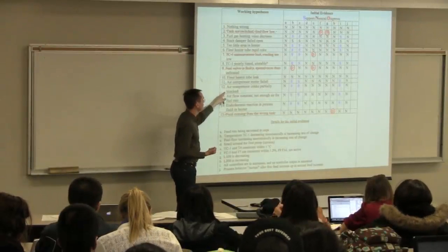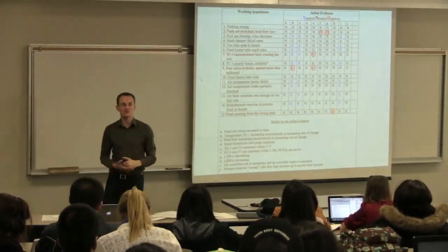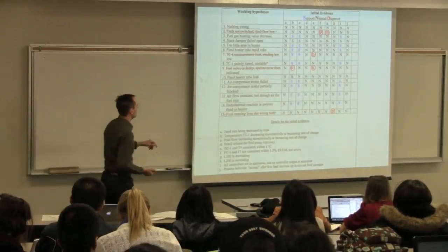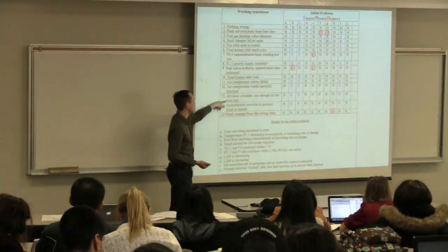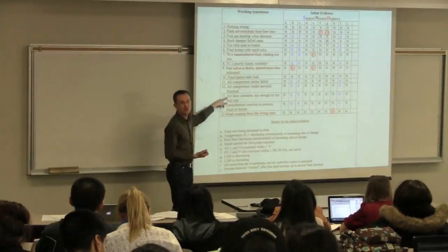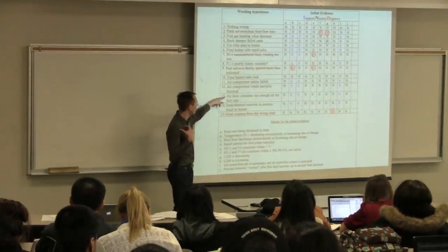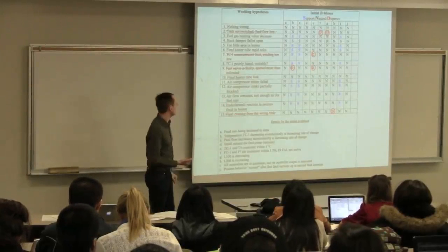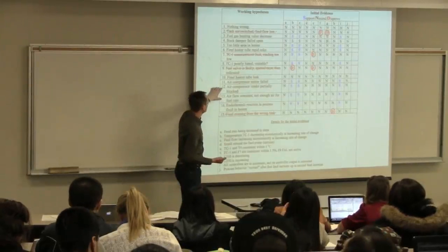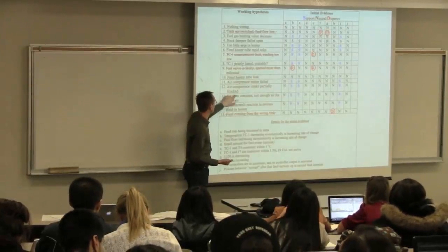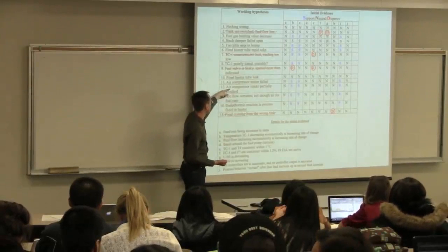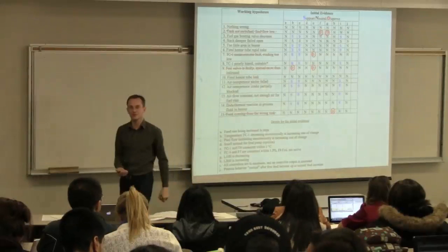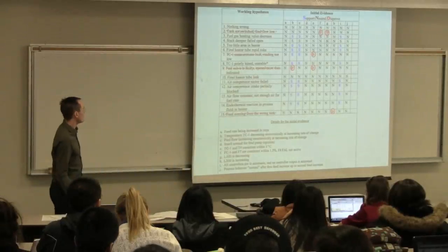The air compressor could have been partially blocked, so the feed air could be partially blocked, or the 13th one down here is that the airflow rate is actually constant, but it's not sufficient to support combustion. So we're adding more fuel than we have air for. So 12 and 13 are similar hypotheses with the same outcome. Either our airflow is blocked, or our airflow is just too little to support the amount of fuel we have going in. So these are all valid hypotheses.